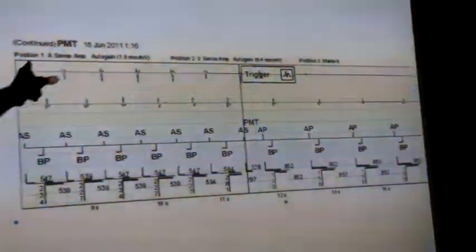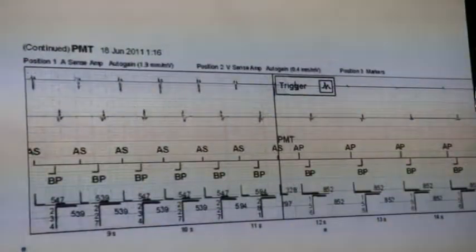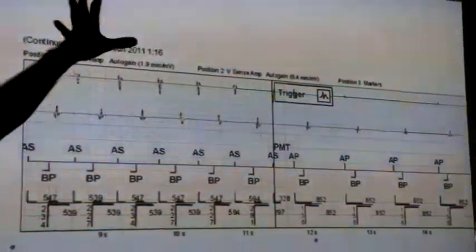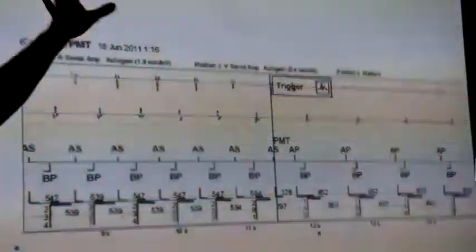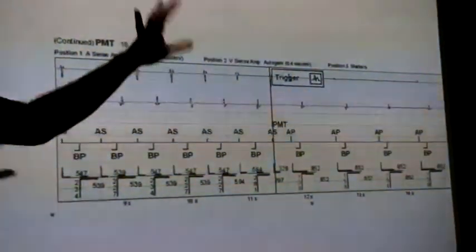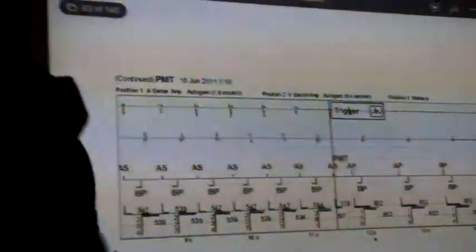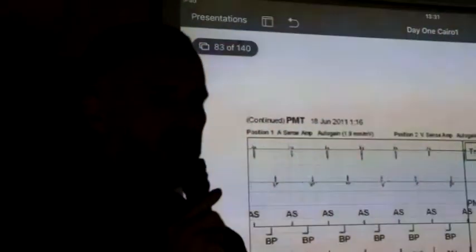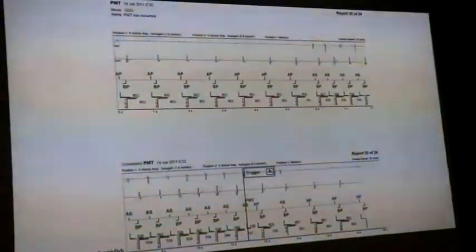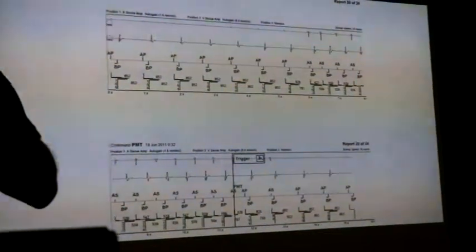You could put a magnet on, yeah, a magnet will stop it. Problem is the patient's at home, and these termination algorithms are always on, and they work really well, okay? So when you see these, if you can fix it and stop it happening, you should, but don't compromise other aspects of the device functionality, okay? And this would be an example when, if you made a change, you'd probably compromise the device a little bit, okay?